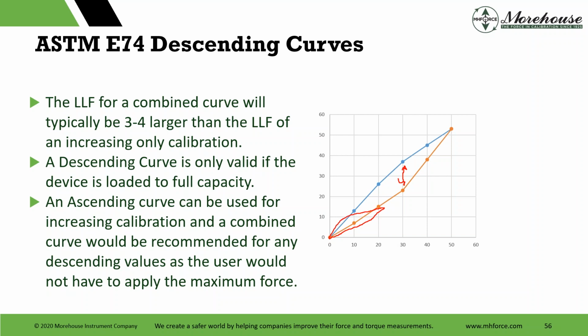A descending curve is only valid if the device is loaded to full capacity. That's true. That's the reason you use a combined curve, because we're going to capture all this error, and we can go to 50% and back down. Right there, I just showed my drawing was off. But if we go, this is the increasing. If we go up to 50%, typically we come back down. It's going to go like this. Kind of starts looking like a whale after a while, depending on how you draw these.